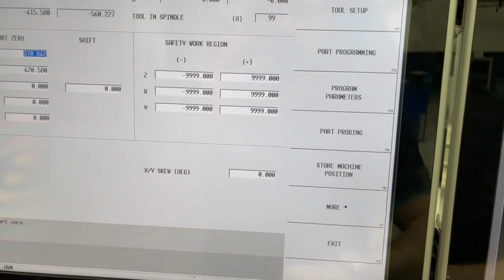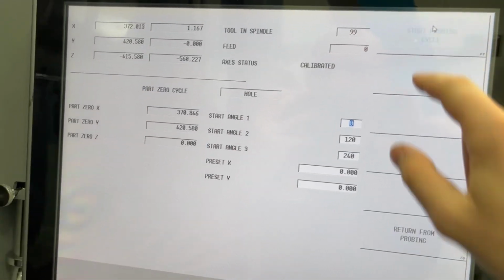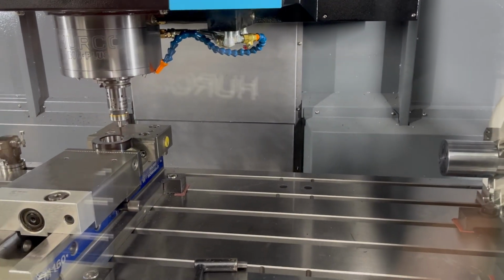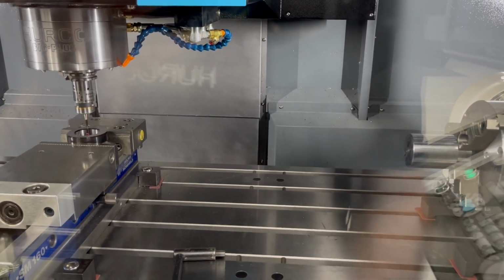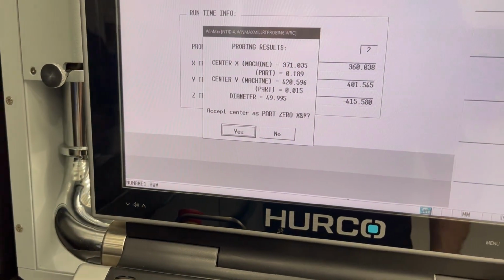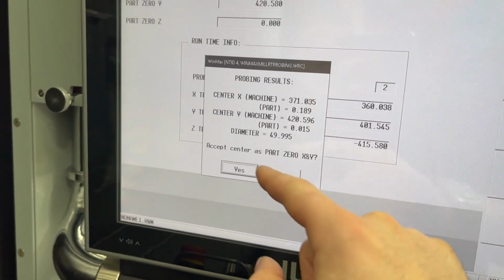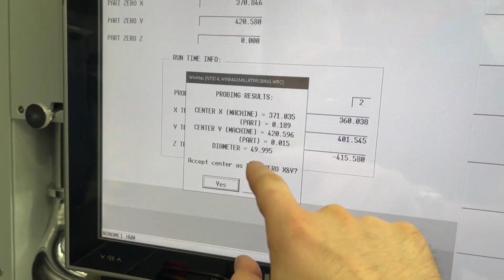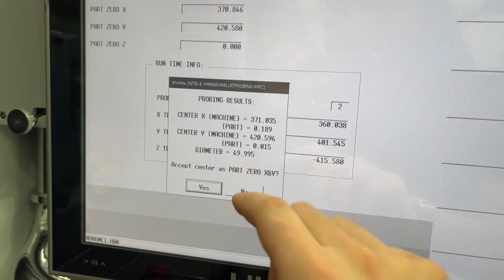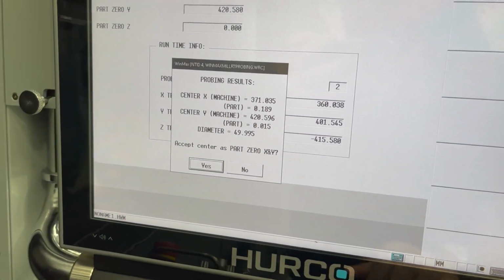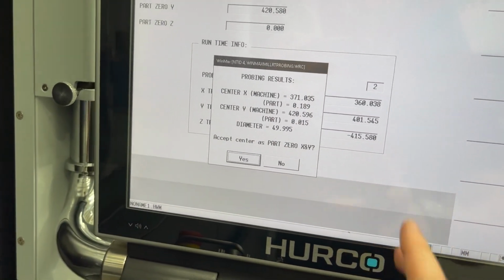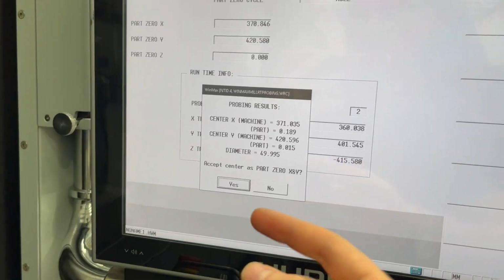And once we've got those deflection offsets in there, that is the probe set up for doing diameters now. It's not the Z, we haven't done anything to do with the Z yet, that's just the diameter done. So what I like to do is I just like to run a little circular probing cycle, just to make sure that essentially it doesn't find a different center point for that gauge. You want to just make sure it stays in the same place and also make sure that it reads the correct diameter of the gauge. So my gauge is 49.995 or 96 I think it was, and it's picked that up. So I'm happy with that. I'm happy that that's set, and now we're going to continue on to setting the Z up.